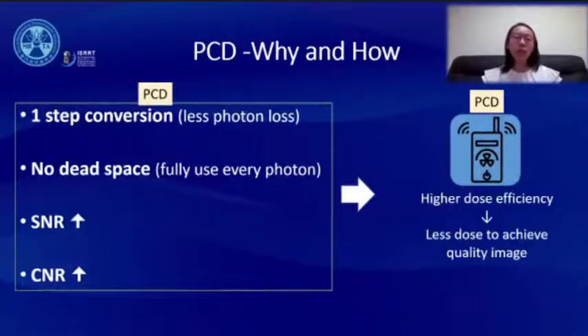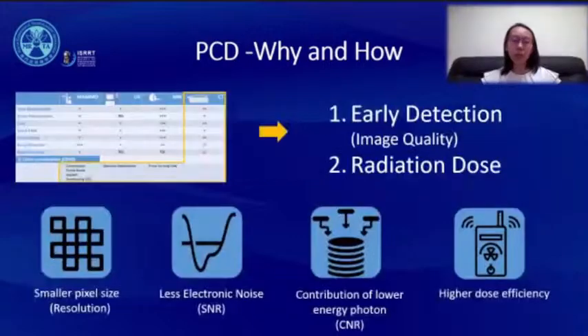The structure and the signal generation mechanism of PCD make better use of every photon coming into the detector. The dose efficiency is higher then. The SNR and CNR are also improved at the same time. From another point of view, less radiation dose can be applied to get the same quality image in PCD. The image quality and dose performance are what we are concerned about the most for putting CT into breast imaging. As we can see, PCD provides better performance than the traditional EID detector. So, overall speaking, how is the performance of breast CT with PCD compared to mammogram?